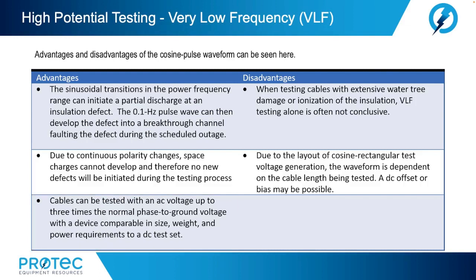Now, among the disadvantages of the cosine pulse wave, when testing cables with extensive water tree damage or ionization of the insulation, VLF testing alone is often not conclusive. Another disadvantage of the cosine pulse, due to the layout of cosine rectangular test voltage generation, the waveform is dependent on the cable length being tested. A DC offset or bias may be possible.